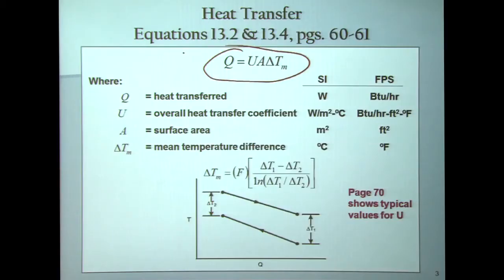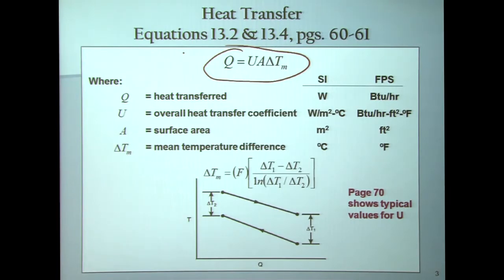Q is the heat transferred from one stream to the other — it's called the duty, the rate of heat transfer. U is the overall heat transfer coefficient; it's essentially the inverse of the resistance that the heat faces when going from one stream to the other. A is the surface area of your heat exchanger, and delta T mean is your driving force, or your mean temperature difference.